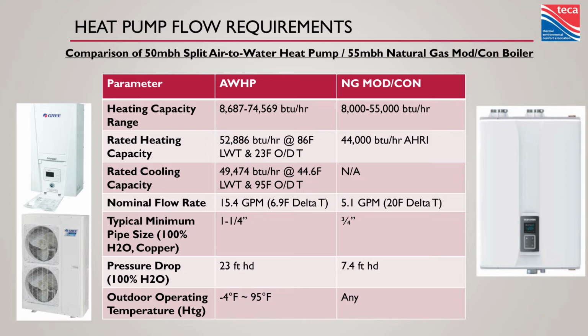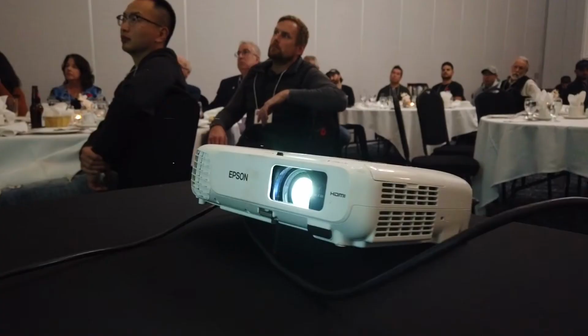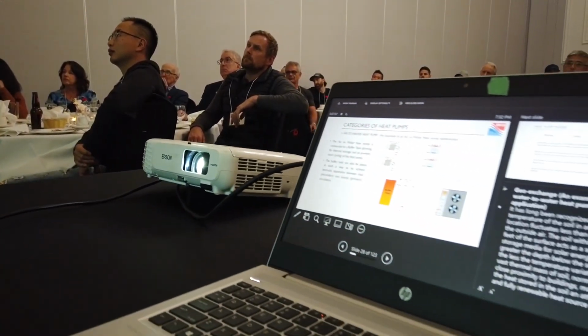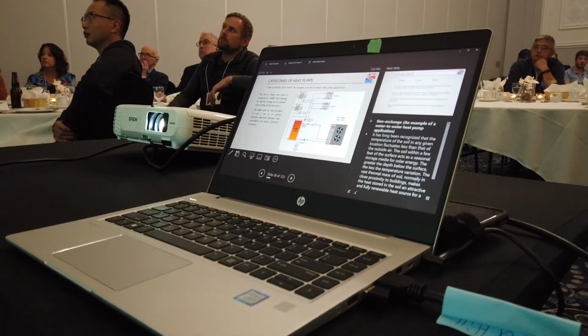This is a water tube boiler, so pretty high pressure drop in the boiler world. 7.4 feet of head at that 5 gallons a minute. 23 feet of head through that heat pump. Now we are moving more flow, but we are going to be using a larger pump for this than that other boiler. Operating temperature range. In heating mode, this thing can create heat anywhere from -4 Fahrenheit to 95 Fahrenheit outside. The boiler doesn't care.